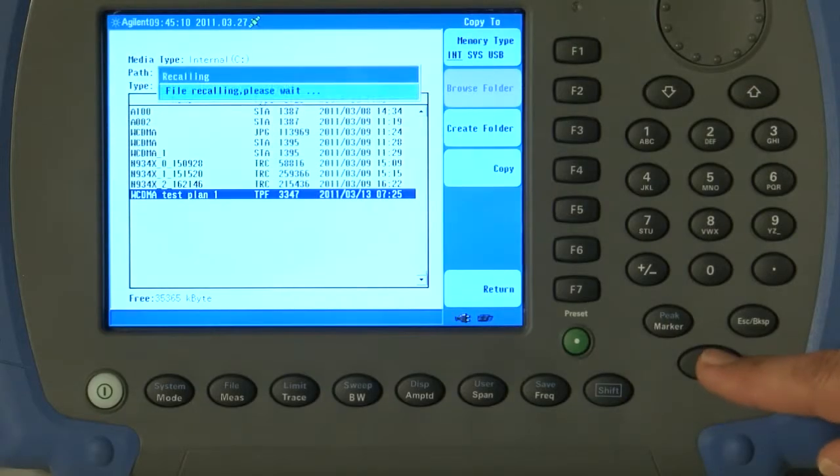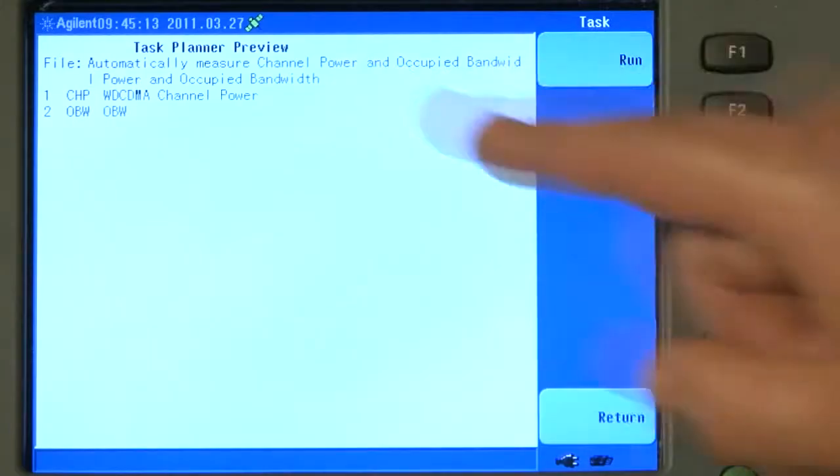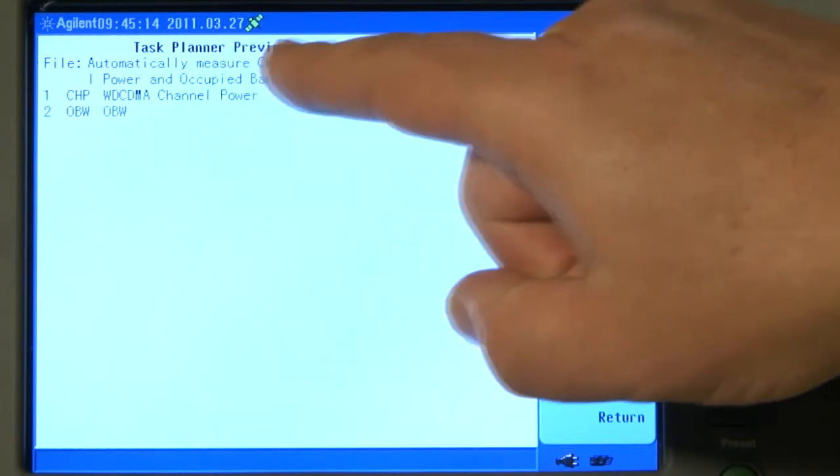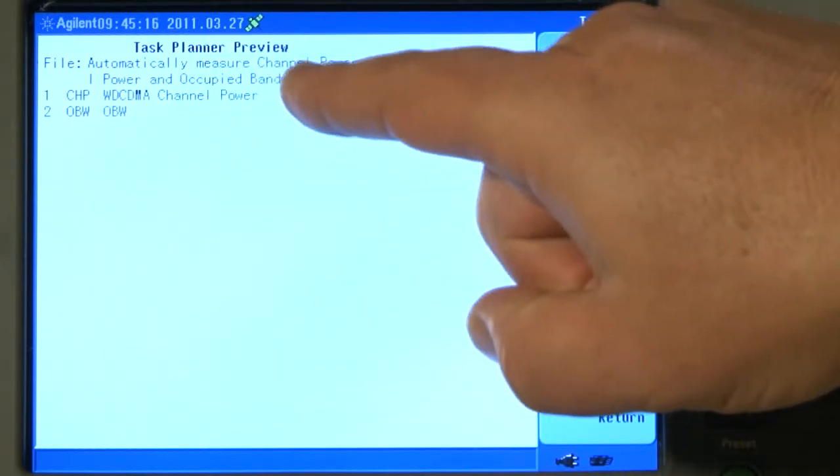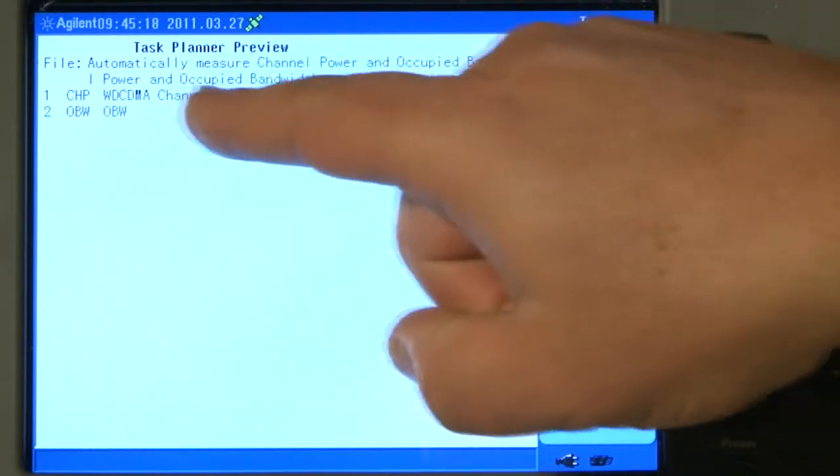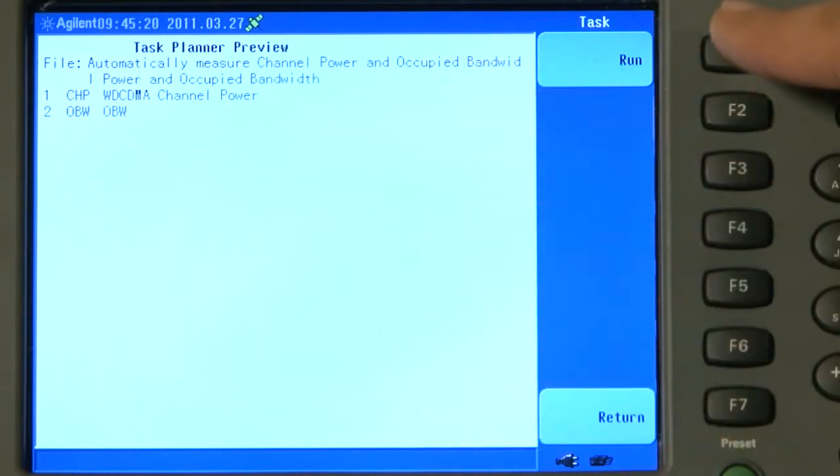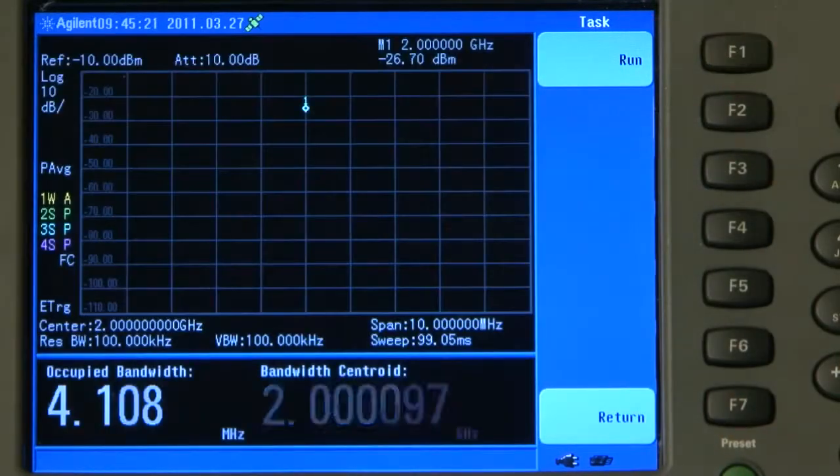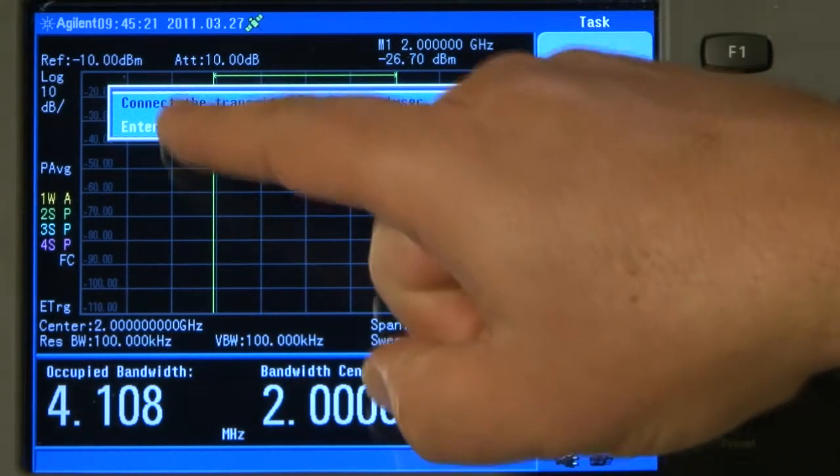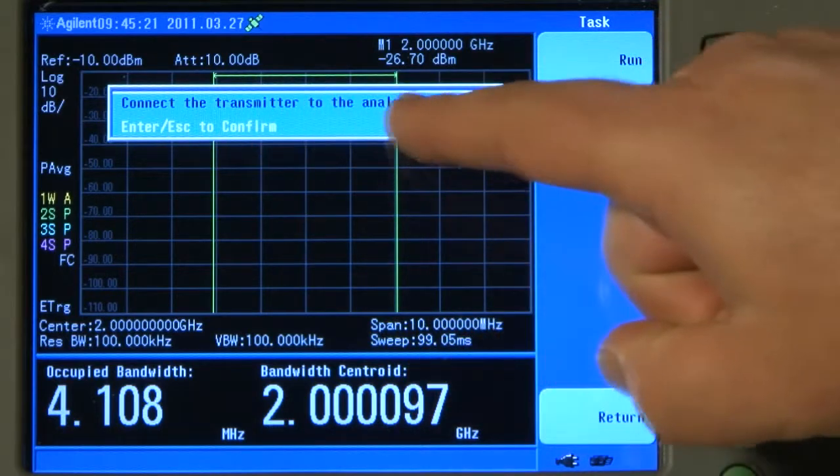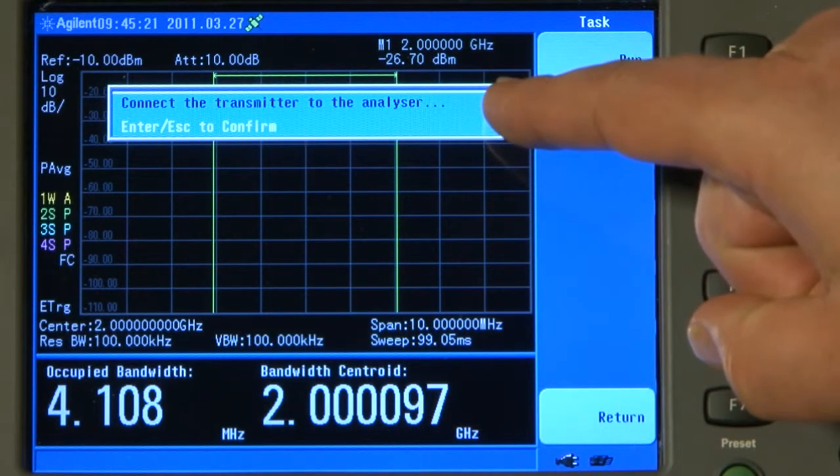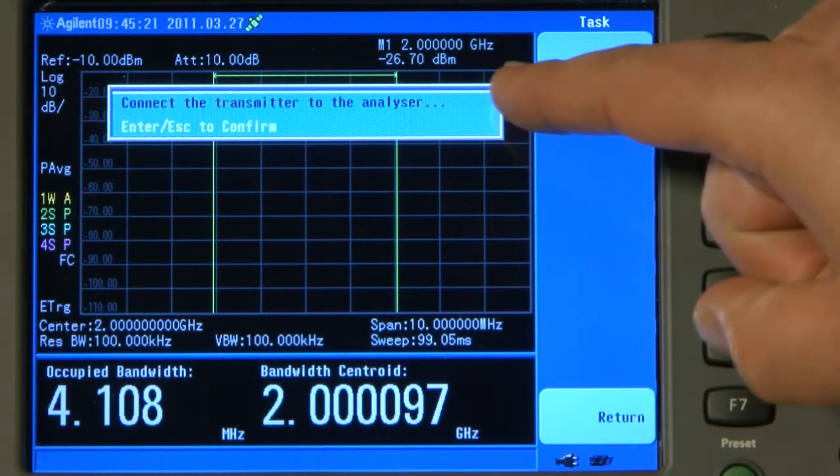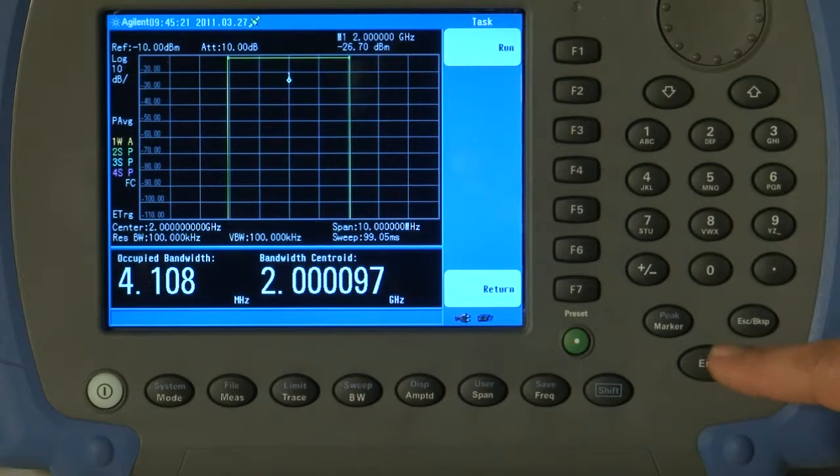If I press Enter, you will see here it says Task Planner Overview. It gives the name of the task plan, the description we gave it, and the two tasks. So if I press Run, it says here the instruction that we typed in for the operator, connect the transmitter to the analyzer. So we will connect the transmitter and then press Enter.